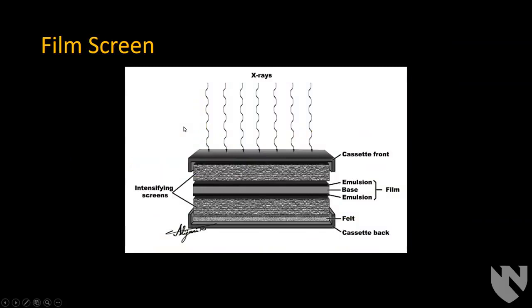Here's an example of what a film screen cassette looks like. The x-rays go through the cassette and hit an intensifying screen, which is a scintillator that turns x-ray energy into visible light energy. There is a film sandwiched between two screens. If the x-rays collide with something in either screen, it creates visible light and exposes the x-ray film in that area.